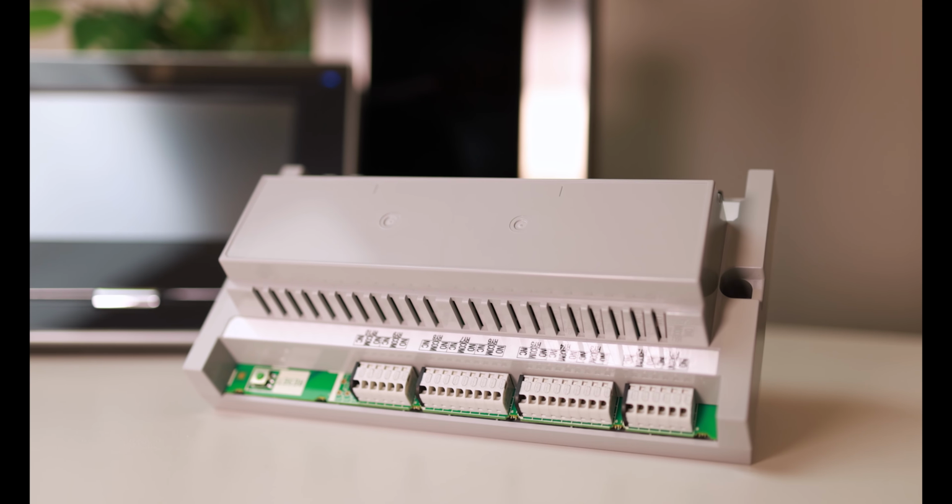Our IXG series stations have built-in door release relays. We can use the triggering of these door release relays to send SIP signals over the network to our IXW-MAA multipurpose relay adapter. This allows us to use the relays on that adapter to trigger door release as opposed to the relays that are built into our door stations.